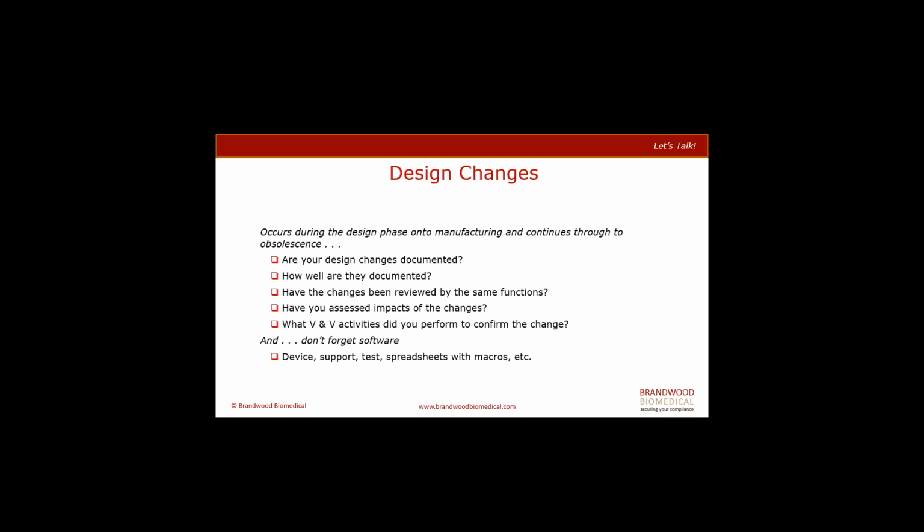Design changes. They occur during the design phase, onto manufacturing, and continue through to the obsolescence of the device. It doesn't just stop when the DHF, or the design history file, has been compiled and the project moves into manufacturing. It is right through to the obsolescence of the product.